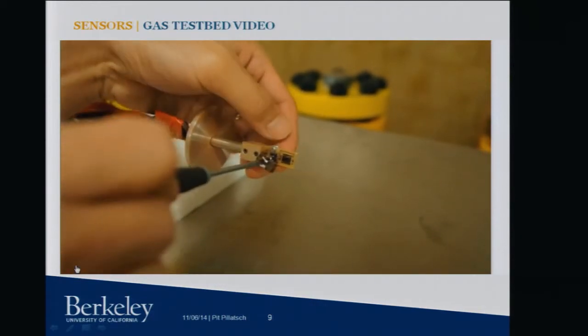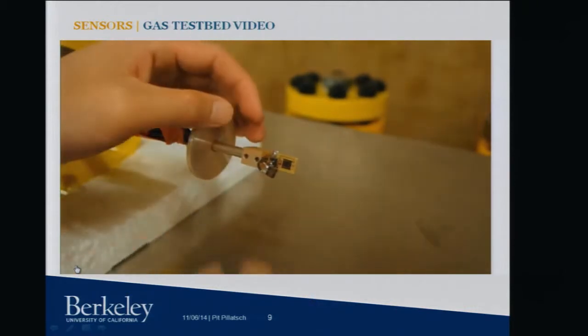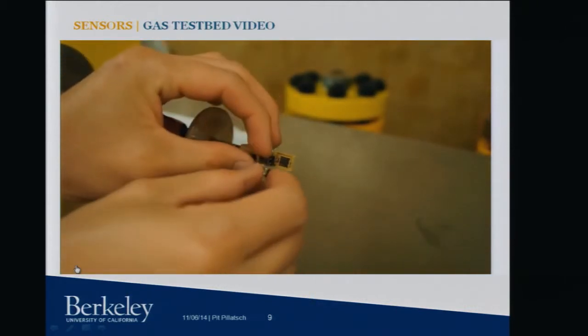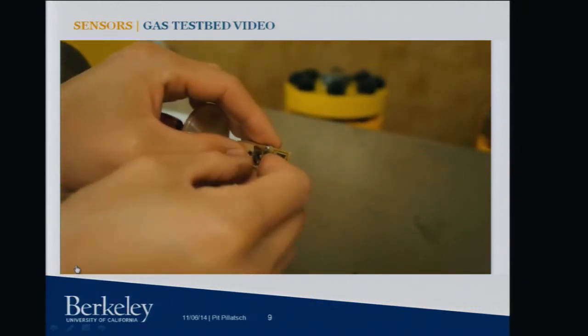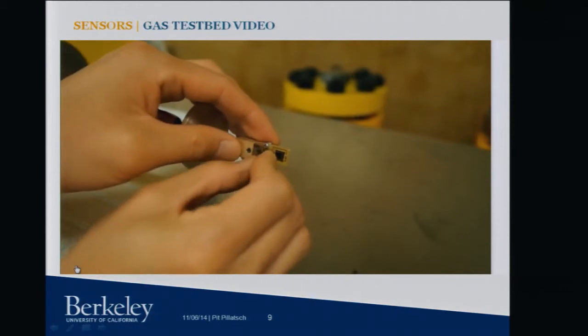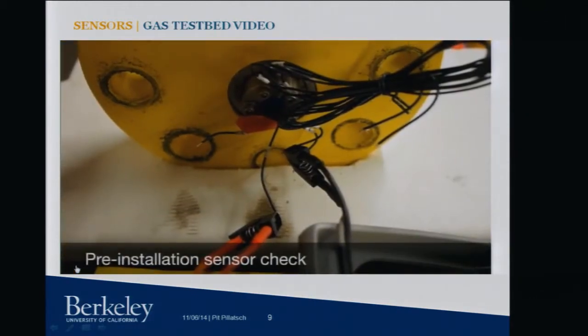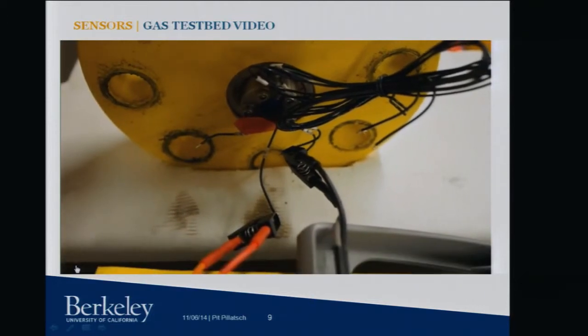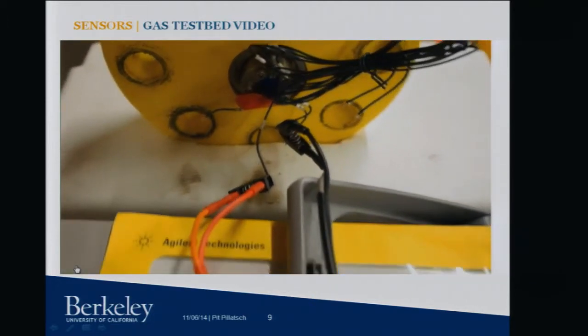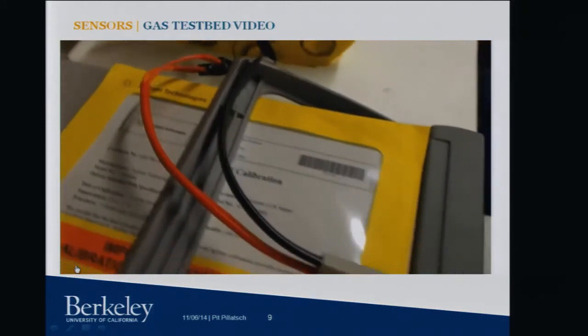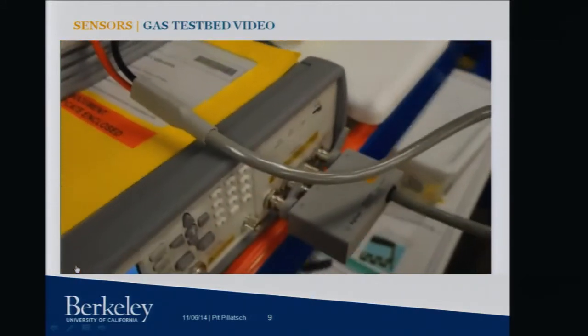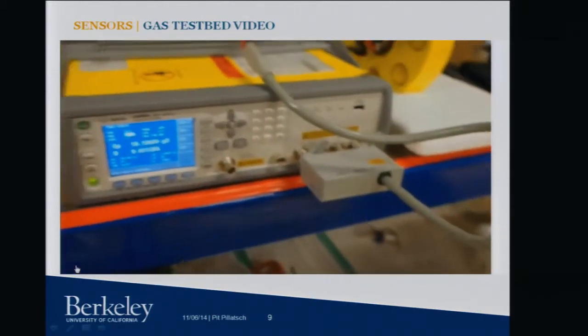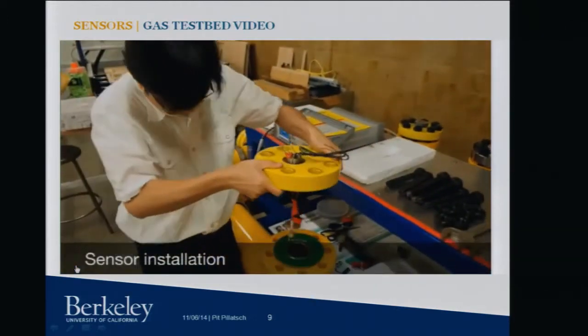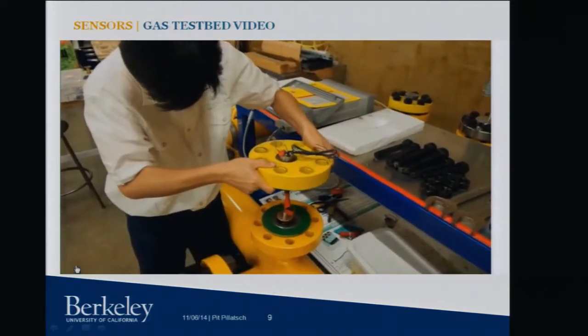So yeah, this is the flow sensor doing the electrical connections. This is connected to the component analyzer to actually measure the capacitance before putting everything back together — just doing a sanity check that everything is working properly as we expect before closing it up, because it's a bit of an effort to put all the bolts back in.